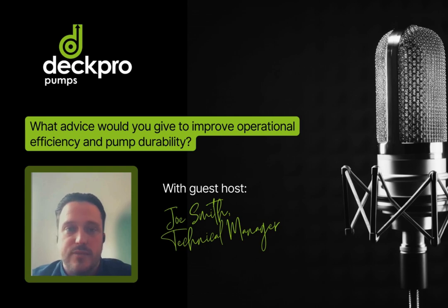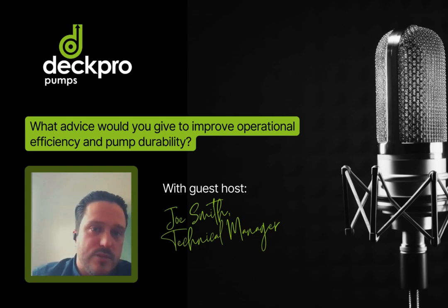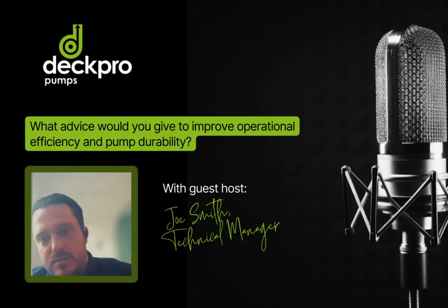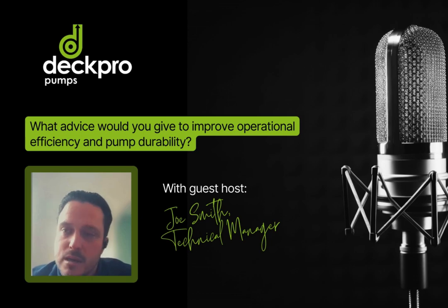It's worth considering, if a pump's noisy, react straight away. If a pump's leaking, react straight away. Often a small problem is an easy fix, quicker turnaround, and you're back up and running. Not acting straight away can lead to a bigger problem, and then a longer lead time, longer repair.